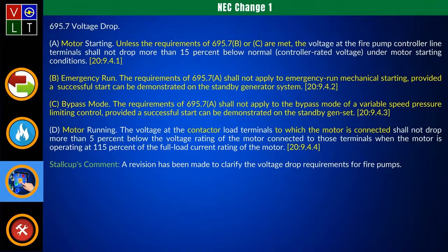All right. Now, what they did here, they made a revision to help clarify the voltage drop requirements when we're dealing with fire pumps. Basically, you've got a voltage drop for motor starting, then one for emergency run, then one for bypass mode, and then motor running. And now that they made the changes, I might look at putting together a video where we show how to do the voltage drop for motor starting.